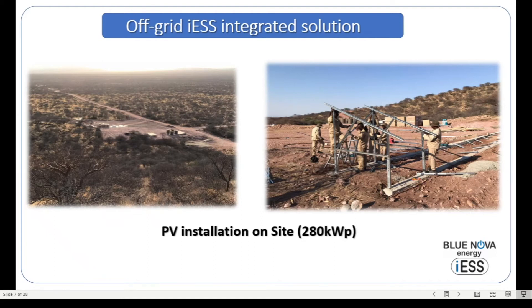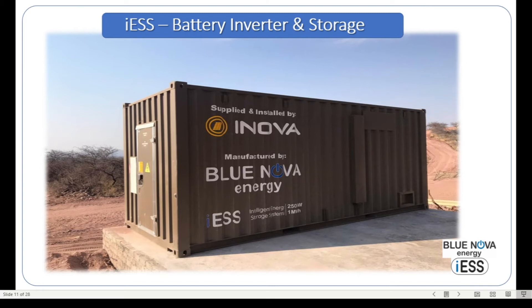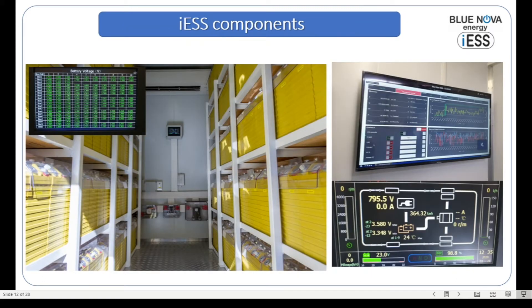The system in this example has a 280-kilowatt-peak solar array being installed just north of Windhoek. Together with those PV array systems, we have five 60-kilowatt-peak AC-coupled MPPTs. Each one of these MPPTs has six-channel input, so we have the ability to deal with at least 30 arrays in this scenario. We also have the battery inverter and storage component, which is the integrated ESS — the iESS system — deployed on a cement slab as seen in the picture.